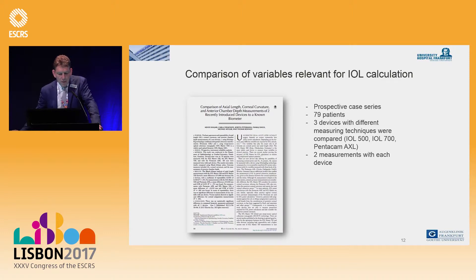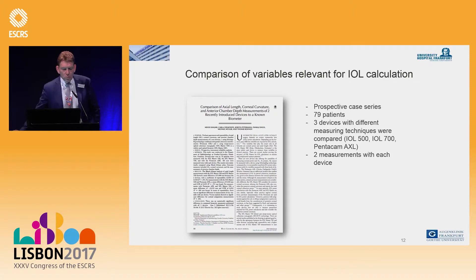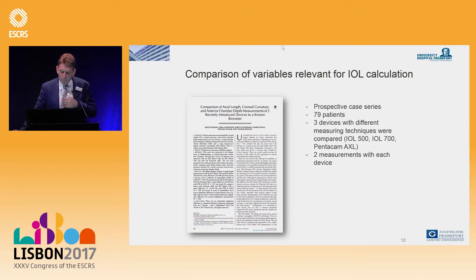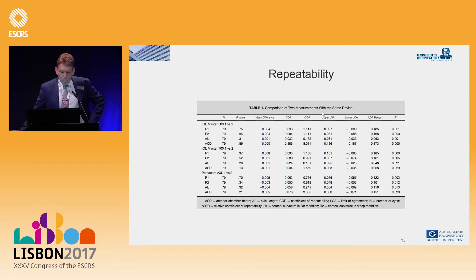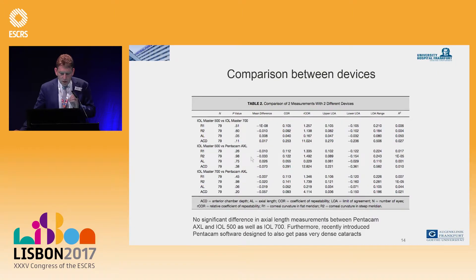Comparing variables relevant to IOL calculations: a paper published in AJO compared axial lengths, corneal curvature, and anterior chamber depth measurements from two recently introduced devices against a known biometer — the IOL Master 500, 700, and the Pentacam AXL. In this prospective case series of 79 eyes with power calculation prior to the study, we found a very good correlation between the IOL Master 500, 700, and AXL for all parameters.